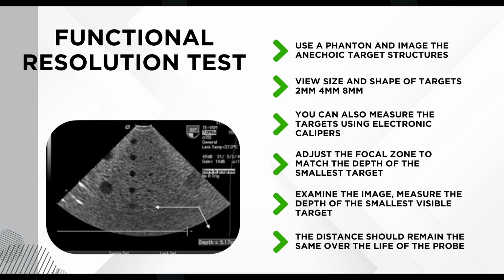You can measure the targets using the electronic calipers, adjust the focal zones to match the depth of the smallest target, examine the image, measure the depth of the smallest visible target. The distance should remain the same over the lifetime of the probe. So in this particular test, you can see they're hitting these small 2 millimeter targets. They increase their depth to the smallest one that they could see. And then they measured the distance. See here the depth. They measured the distance from the top here to the bottom here. And this is just a functional resolution of the transducer here.